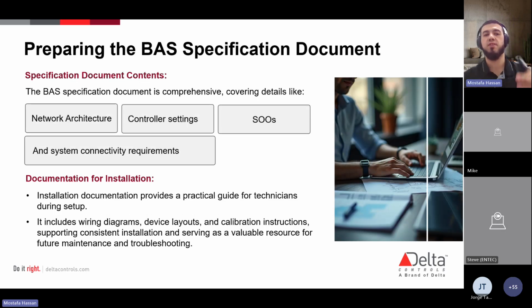Now, overall, you have your sequence of operation, which is a part of a huge specification document, right? It's a guide detailing every aspect of the building automation system, and that's going to include network architecture, controller settings, then your sequence of operation, your device integration requirements, right? Maybe your security requirements. We mentioned BACnet Secure Connect yesterday. Maybe you're going to specify BACnet Secure Connect. This is all going to be a part of your specification document. This document is going to lay out all the components, roles within the system, and connectivity requirements. And this is again going to allow for seamless installation and operation.